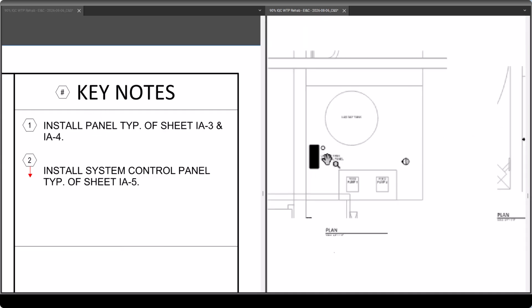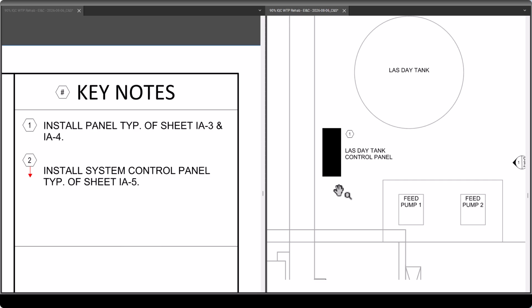So if I'm going to install this, what do I need to install it? How am I installing this? Who's providing this? So would you need to call out the spec at this point? It would be helpful to either, if you don't have particular information in the drawings, you do need to reference the spec, especially if you do have that information.